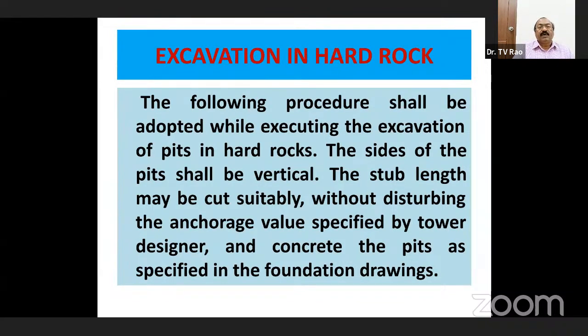That's why the following procedure shall be adopted while executing the excavation of pits in hard rocks. The sides of the pits shall be vertical. The stub length - stub means the angle which comes from the tower leg, that is steel structure, IS angle - may be cut suitably without disturbing the anchorage value specified by tower designer, and concrete the pits as specified in the foundation drawings.